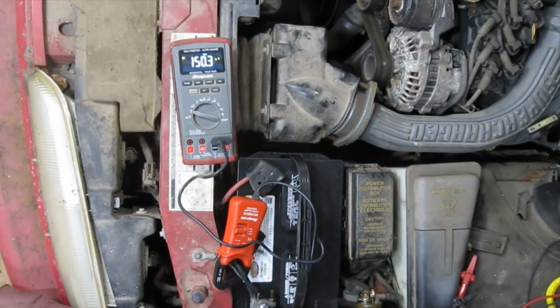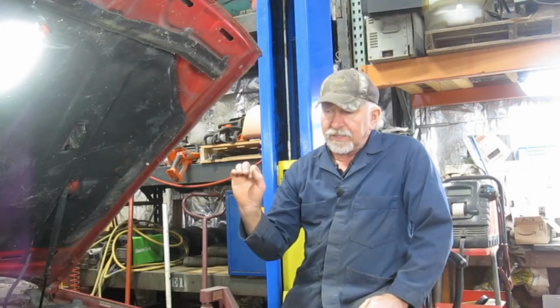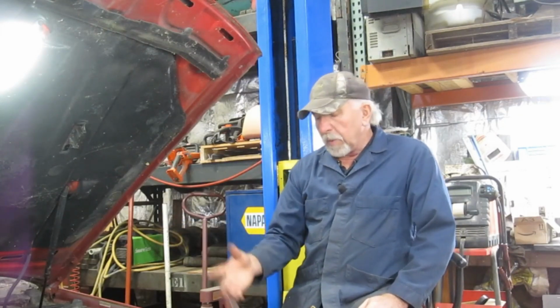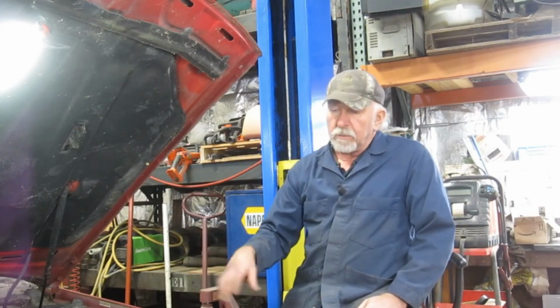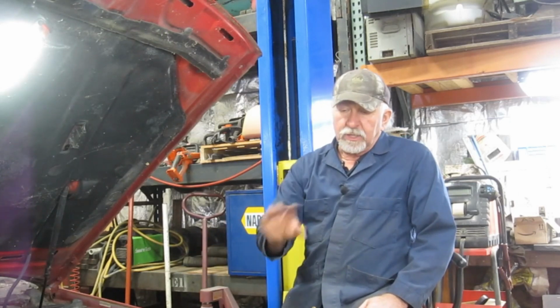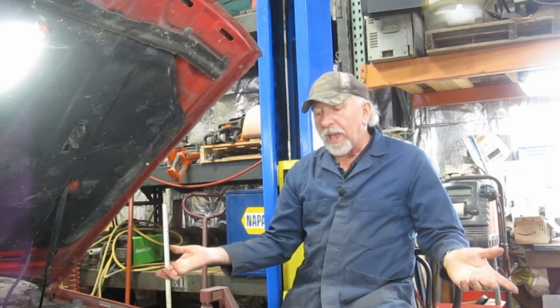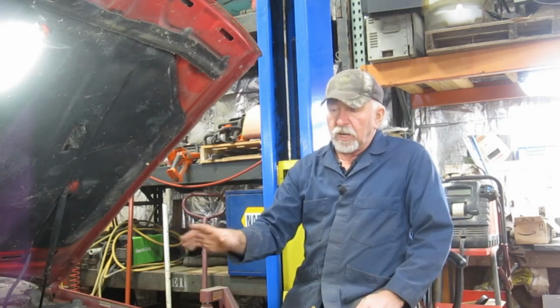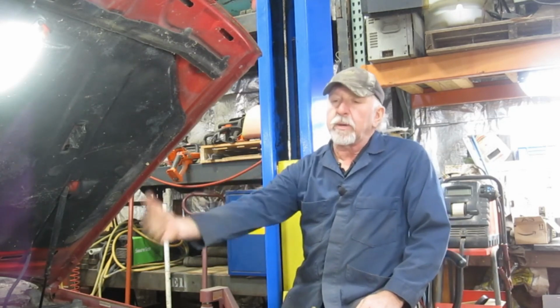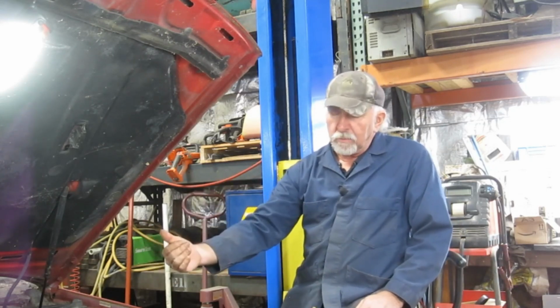We know a lion's share of that is coming from the starter itself. I remember when we earlier tested it, we saw about 40 amps, so we can say that 110 of that is coming from the starter. That tells me we've got good integrity down to the starter from the wires.